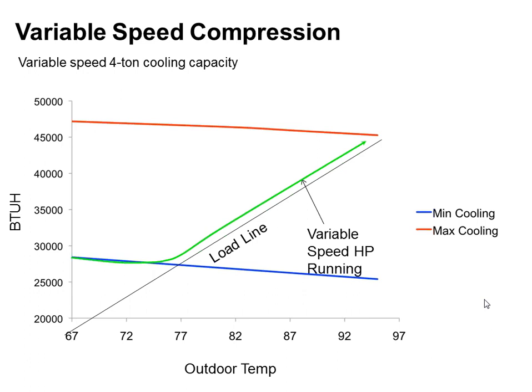What the variable speed heat pump is going to do is try to keep this thing running continuously and never shut it off. By the way, it's going to do the same thing in the wintertime. It's going to try to run continuously and never shut off. That's its whole goal in life, to constantly be running, however, running at much lower capacity, hence saving you tons of airflow energy. So as it gets cooler outside, it'll ramp down instead of cycling off, and as it gets warmer outside, it'll ramp back up the line.